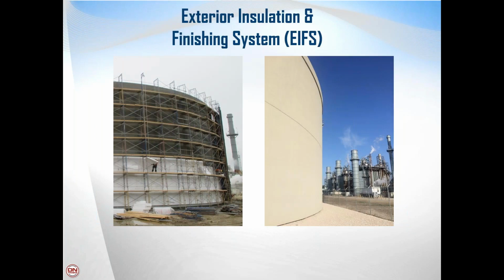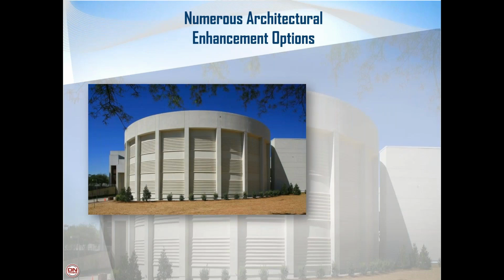And then any of the walls' surface area that is exposed, we insulate the exterior walls of the tank. So to prevent any heat gain in the tank, we will epoxy bond polystyrene board to the outside of the tank wall. And then the very outside surface of that insulation is coated with a cement-like coating to give it a very hard and sturdy outside surface to that insulation. So that any of the wall surface area then will be insulated to prevent that cold water from heating up.